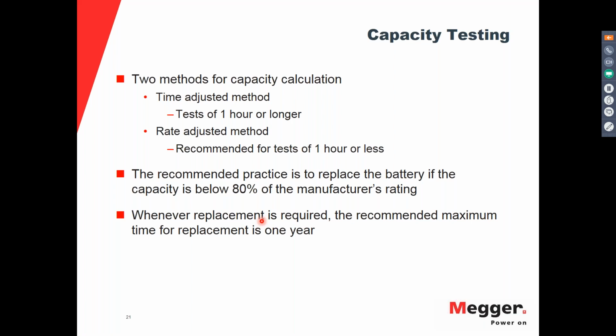However, the rate adjusted method can be used for any type of test and for any duration. And actually, it's a bit more accurate than the time adjusted method. However, that method is more complicated. You need to consider correction factors, so that's why it is not that common.